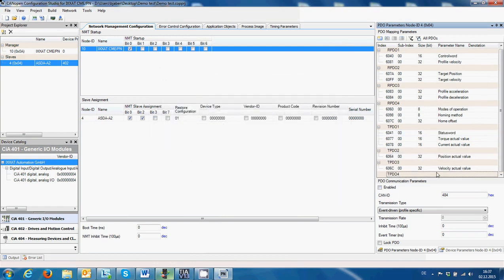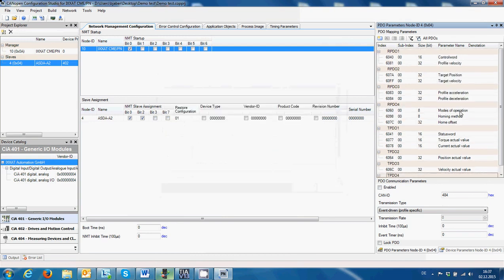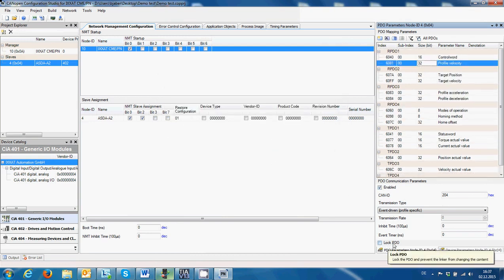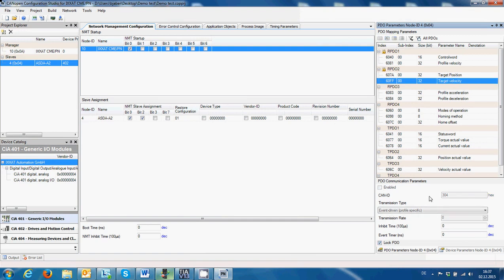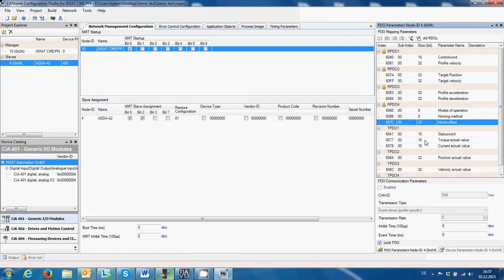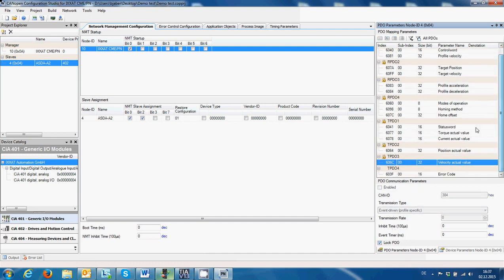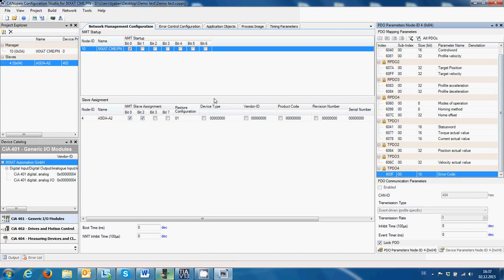Homing Method and Home Offset. The same applies also for the Transmit PDOs. For the station here we're going to add the Error Code. I'm going to press Lock PDO — this will lock the PDO and prevent the program from automatically filling the PDO with other variables.